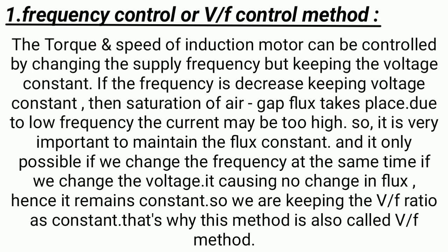This causes no change in flux, and if the flux does not change, no saturation occurs, so it remains constant. So we are keeping the V by F ratio constant. That's why this method is also called the V by F method. That is how we control the speed of three-phase induction motor by this method.